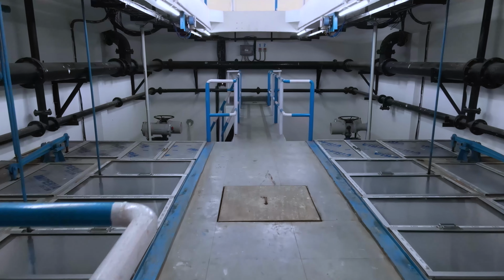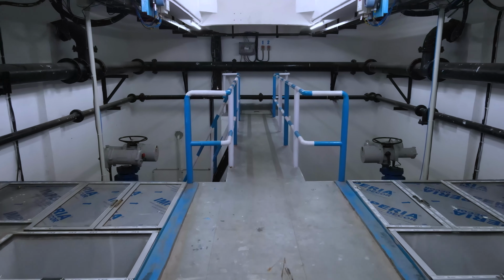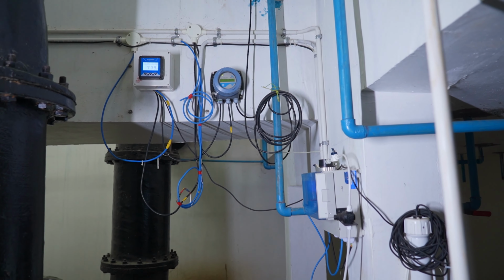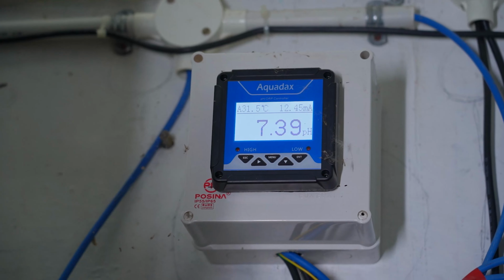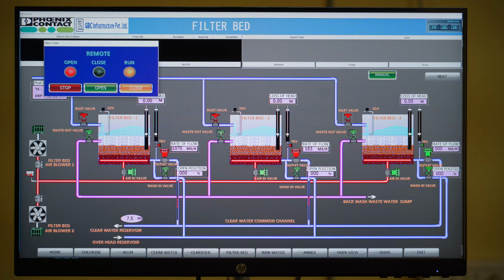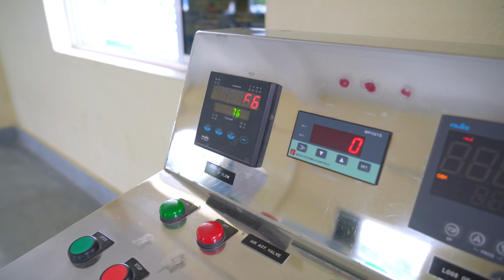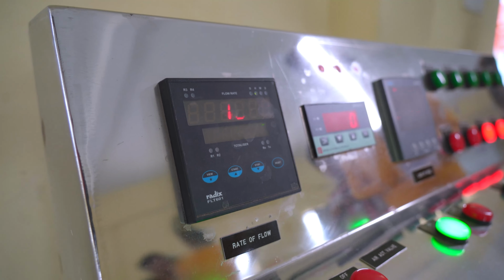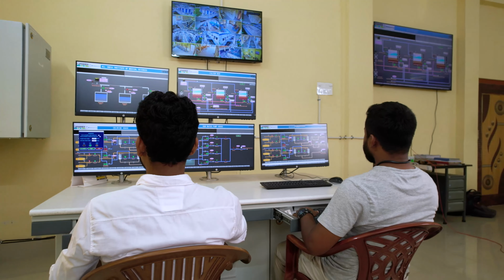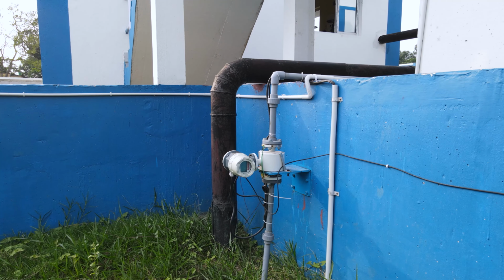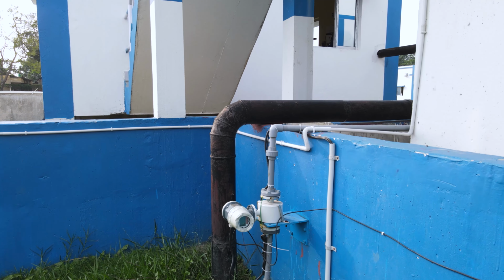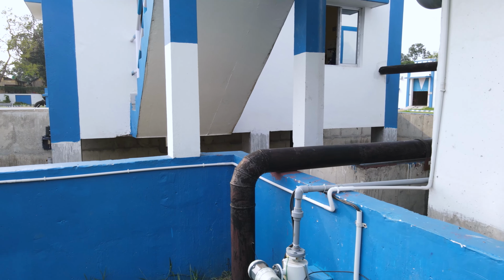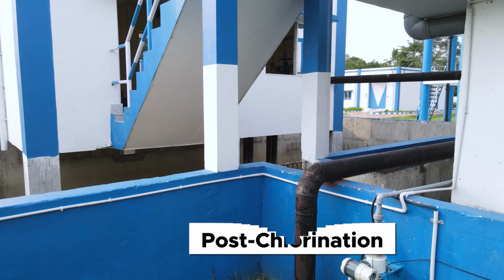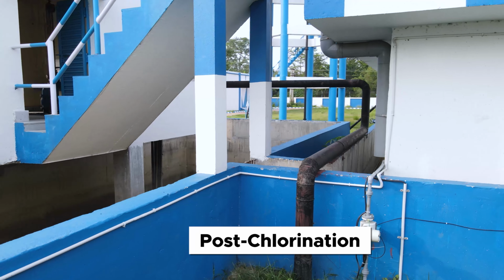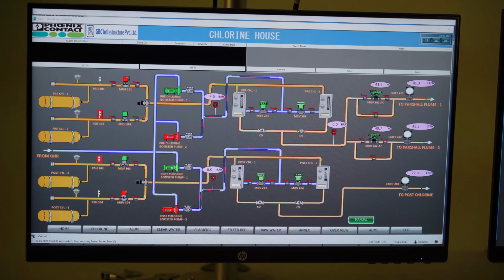the final storage, CWR. While passing through the closed channel, again the turbidity and pH of the final output water are checked online, and the amount of total collected water from the various beds is monitored and recorded by SCADA. The post-chlorination is done here before water enters into CWR. The amount of post-chlorination is decided on the process volume of final water.